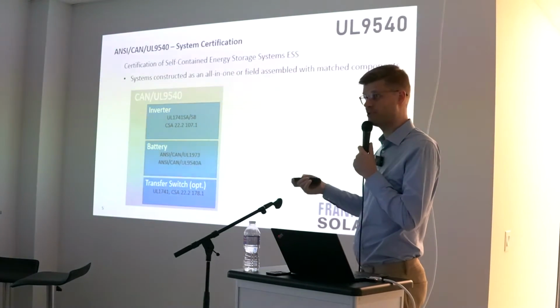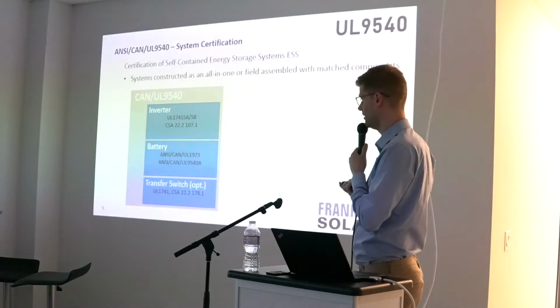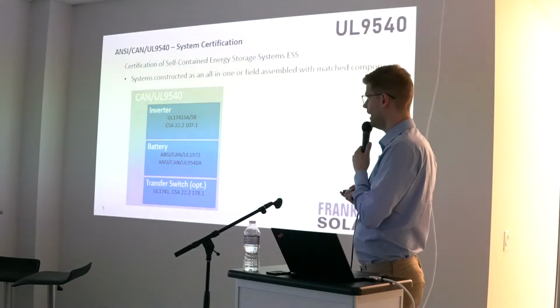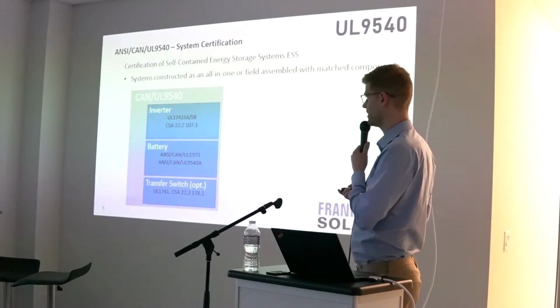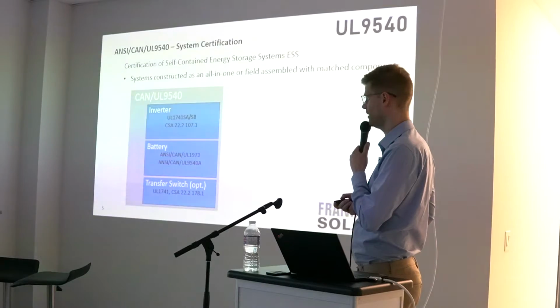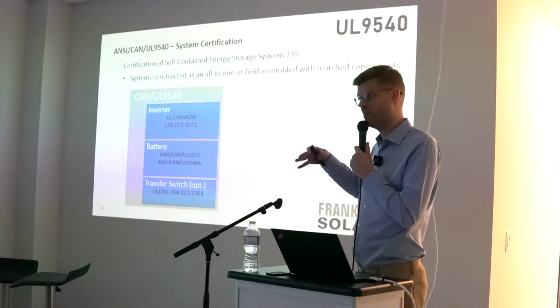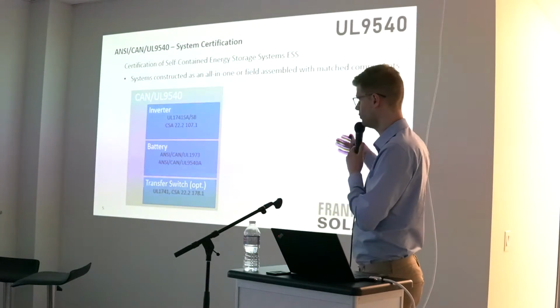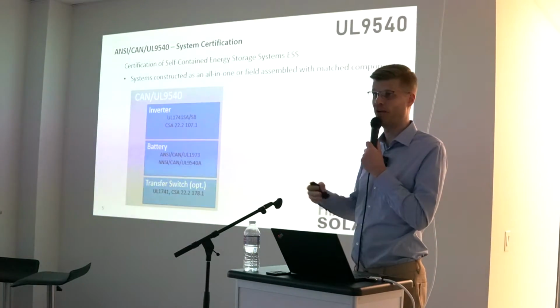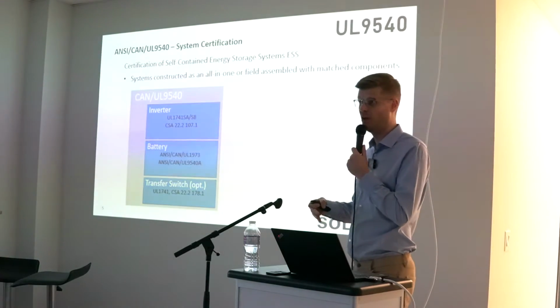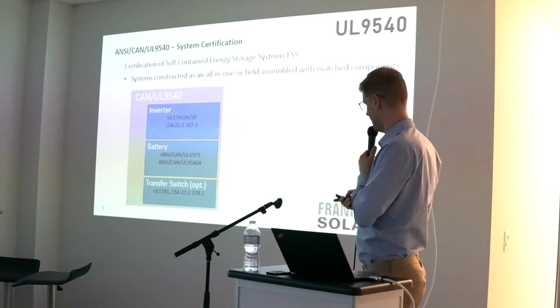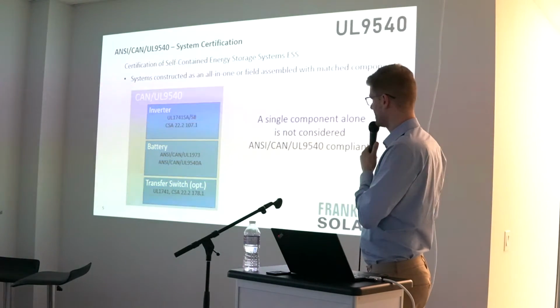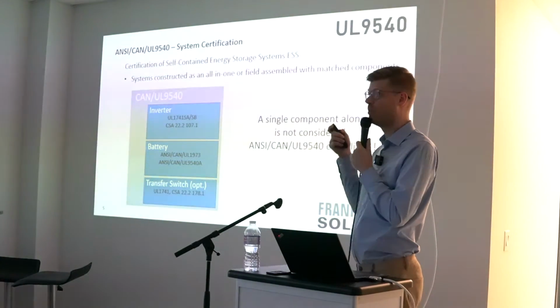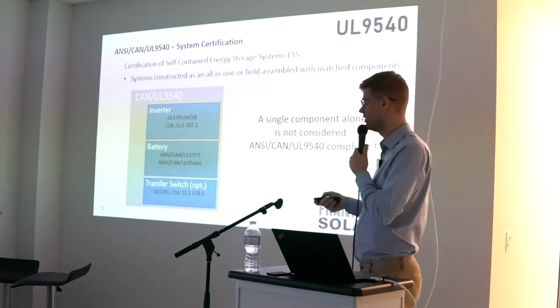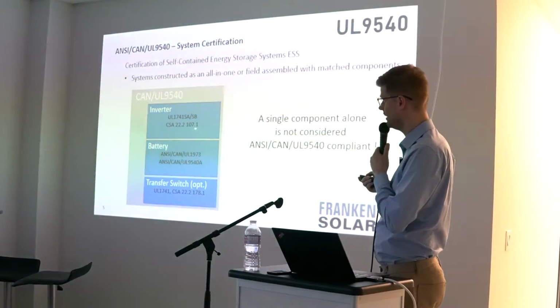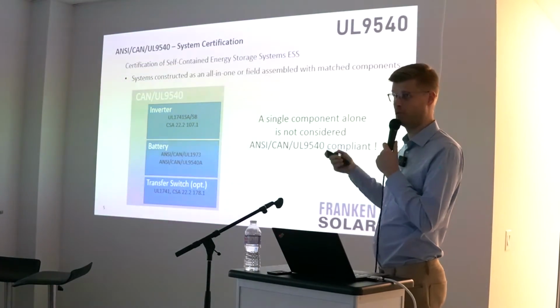The batteries themselves are also certified to their respective UL 1973, and they can be, and most of the newest ones are, to the fire propagation testing of 9540A. And then there are other components that can also be covered in the same document. That might be your transfer switch or an extra cabinet you want to put your battery modules in, or whatever other components are in that system. So the most important thing is UL 9540 is not a component certification. It's a system certification for the interoperability between an inverter with a specific battery or multiple battery modules.